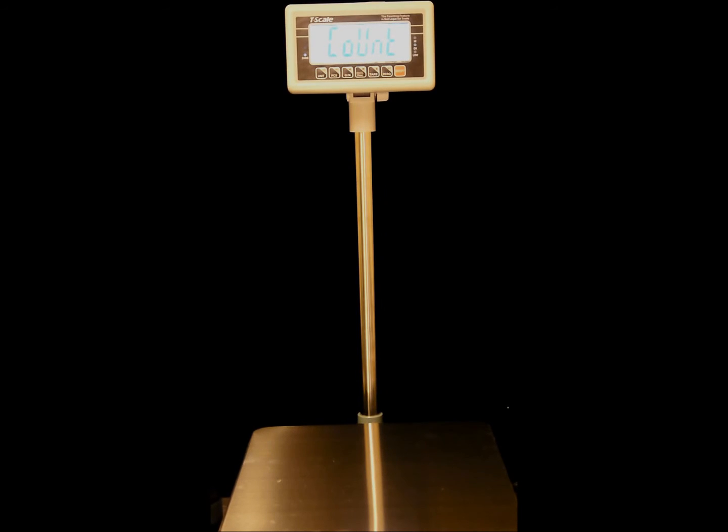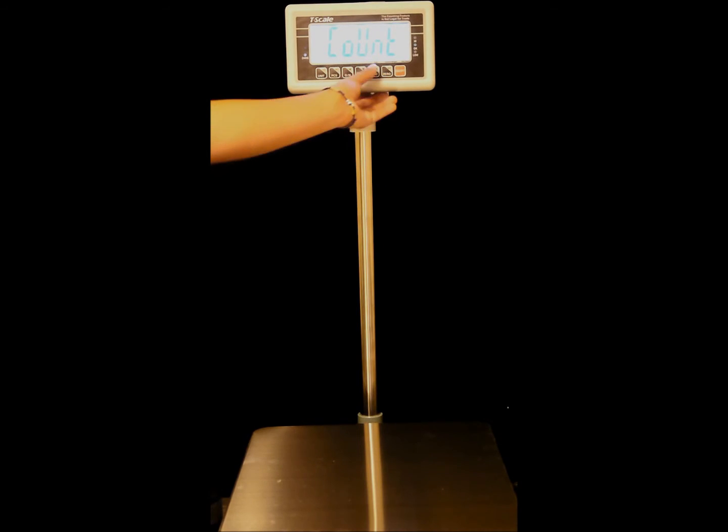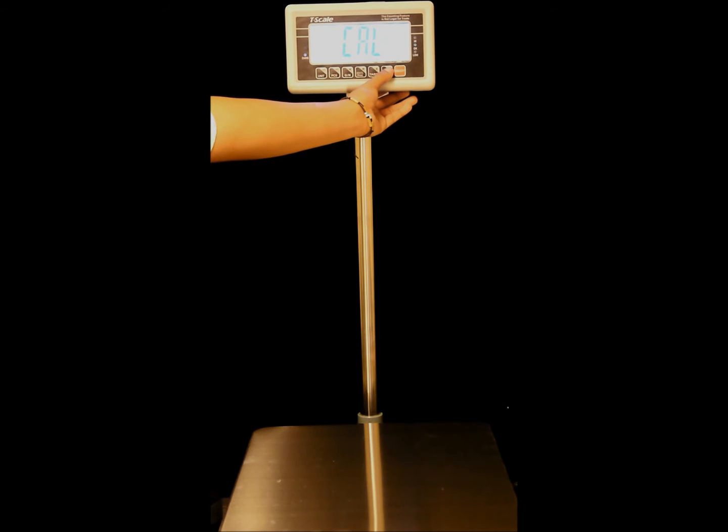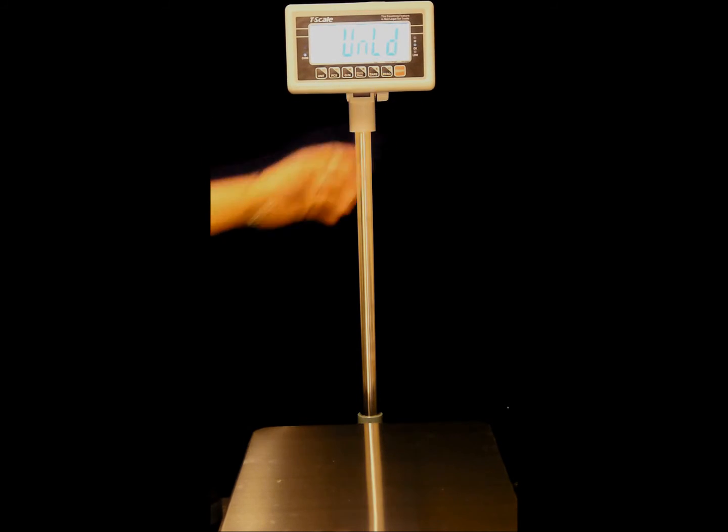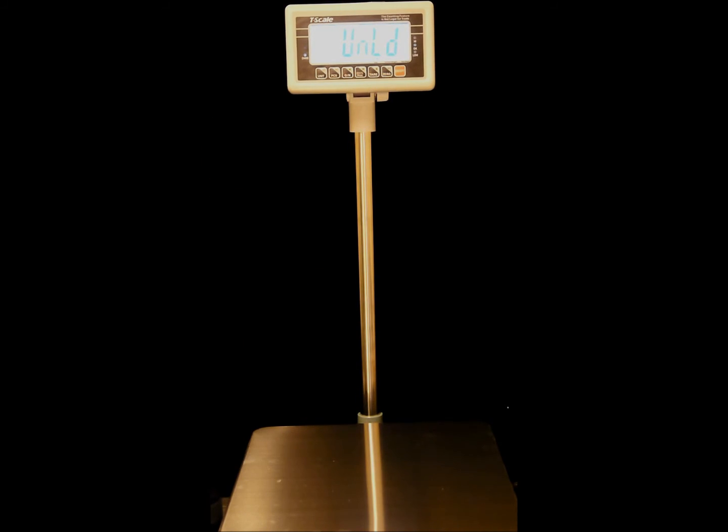Now the display will show CALP. Press the tare key until we see CAL, then press the zero key to confirm calibration. Now the display will show UNLOAD. Make sure nothing is on the platform, and when stable, press the zero key.